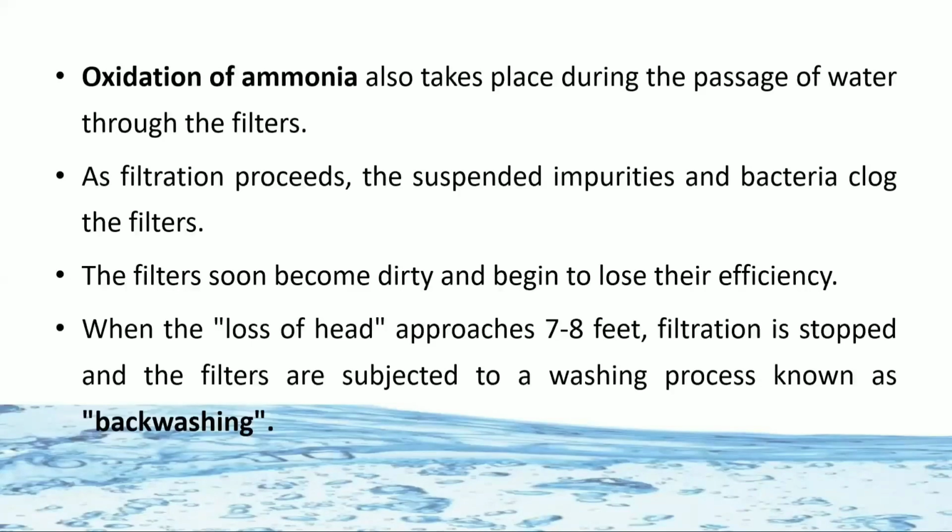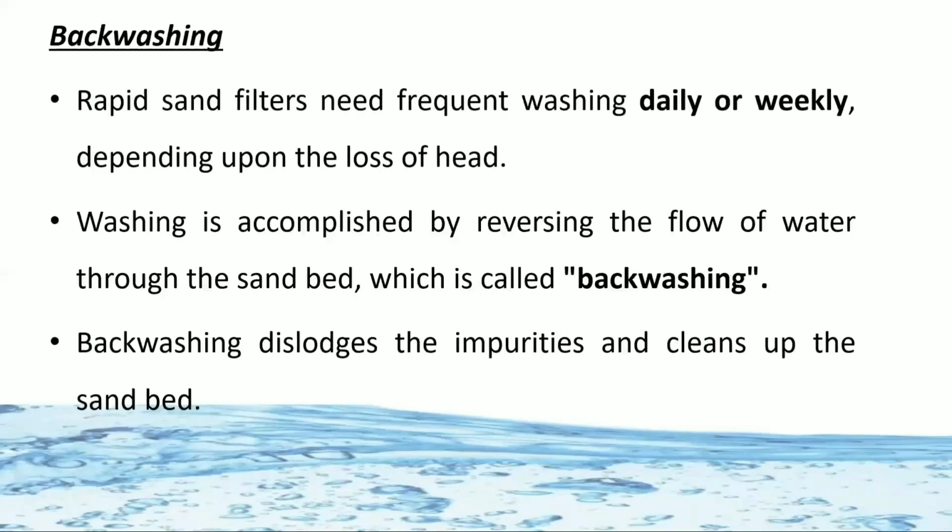So when there is a loss of head and that block is up to 7 to 8 feet, the filtration should be stopped and the filter is subjected to washing. That washing process is known as back washing. The word suggests back washing means reversing the flow of water. So it should be washed daily or weekly.